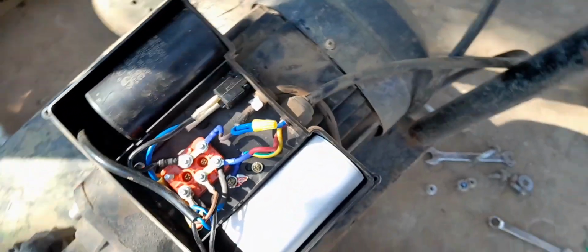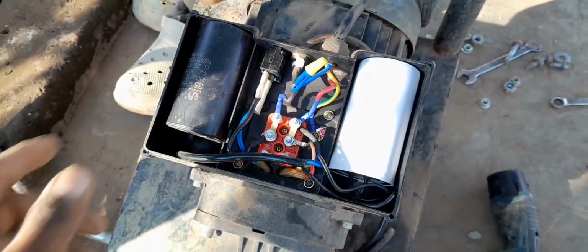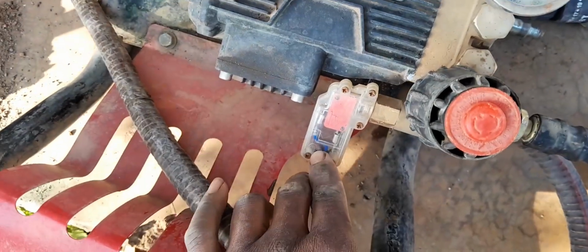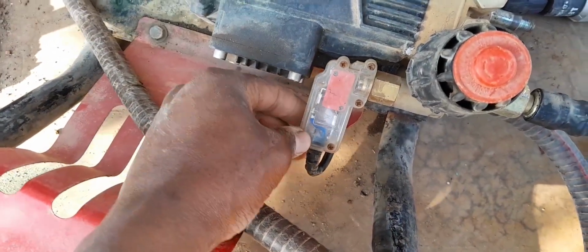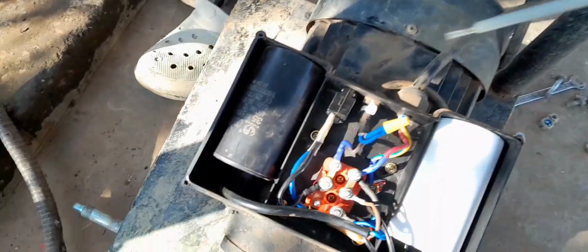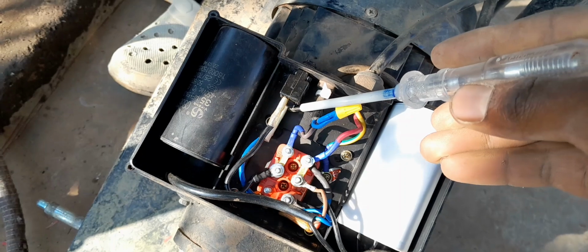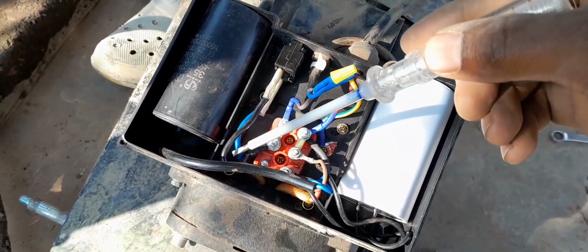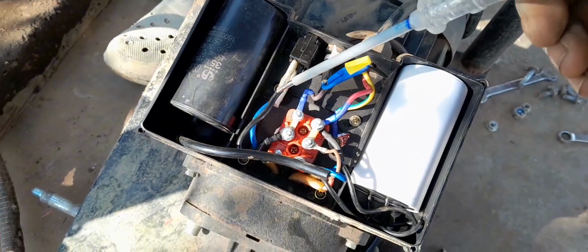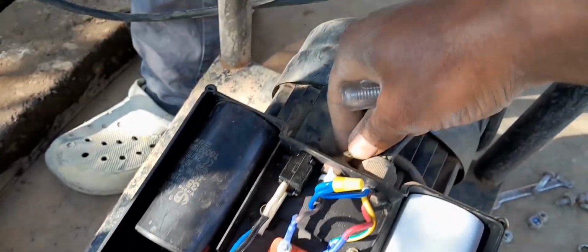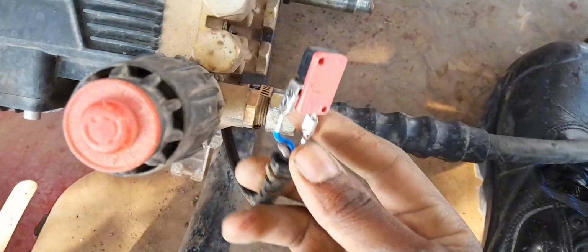This machine has a protective measure so that when water is not going through the pipes, it also trips. And what is that? It is this particular appliance that you can see right here. Inside here, let me open it for you. As I was saying, our neutral comes through here, or our live, or whatever you may want to call it, because it just goes through the winding and comes back through this cable. It comes through this switch here, and then to this terminal, and then comes through this cable, as you can see, and then this cable is this one right here that comes to this particular switch.